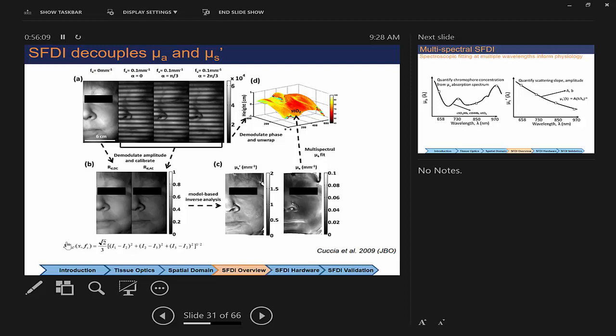I'm not claiming that we have 50 micron pixel resolution, inherent resolution. I would say probably it's 4 or 5 times that, because of the blurring of the light. But there's a decoupling between the spatial resolution of the reflected, this is the diffuse reflectance that's calibrated, this is the absorption and scattering that are calculated, but they're all done at this point-wise location where we have this planar assumption, so that we assume that the optical properties are varying slowly compared to the diffusion of the light. And so we get relatively high resolution photos of absorption and scattering, where we're still using very low spatial frequencies to do the decoupling of absorption and scattering.